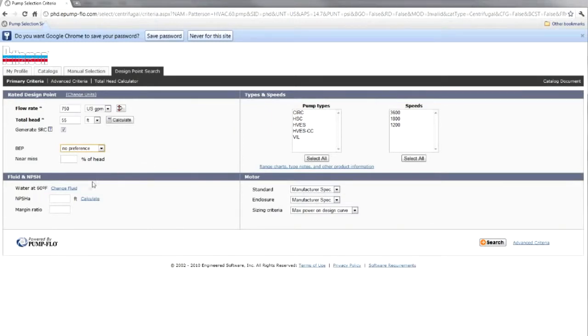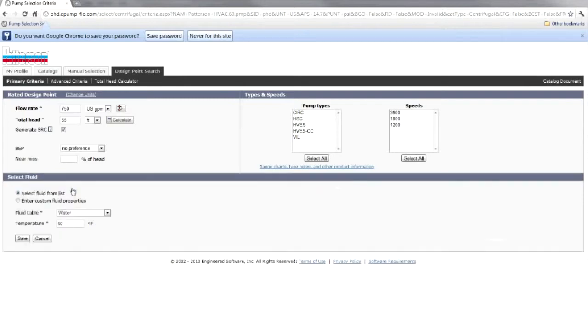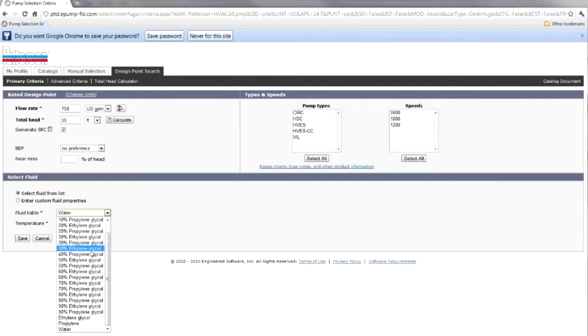The fluid in NPSH right now defaults to 60-degree water, but I'd like to change that because I'm here in Salt Lake City, Utah, and I've got some pretty cold design temperatures. So we're going to select a fluid from the list. If you're pumping some special syrup or something else that you want to plug in some properties for, you could do that with the custom fluid properties. But we're going to drop down this arrow and find 40% propylene glycol.